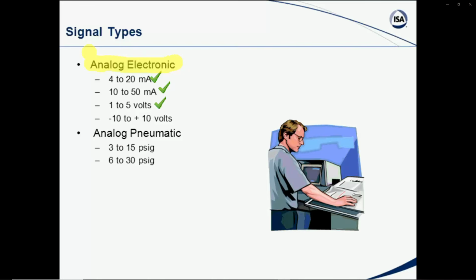You may see 1 to 5 volts. You may see minus 10 to 10. A lot of different signal levels depending on the type of device and the type of transmitter that you have. So we have to be aware of that, as well as also we can have the analog pneumatics. And pretty much they've settled into 3 to 15 pounds. You will see 6 to 30 psig used in some of the pressure valve situations or circumstances where the control valve has to be controlled by a higher pressure.